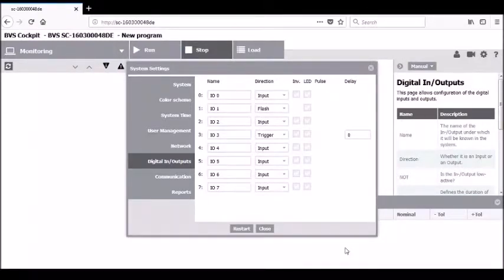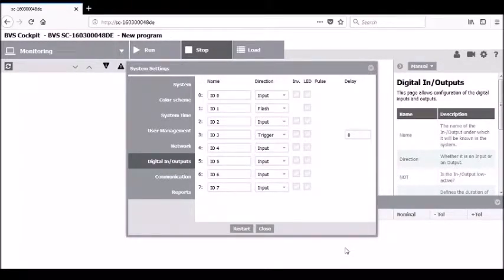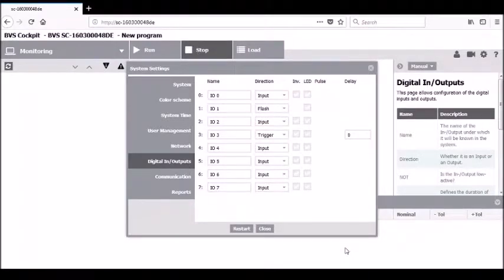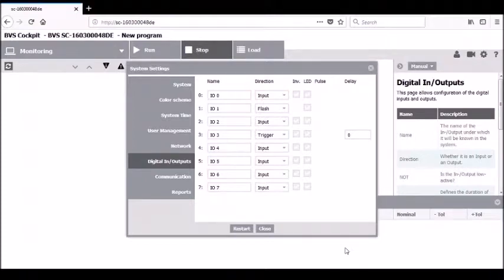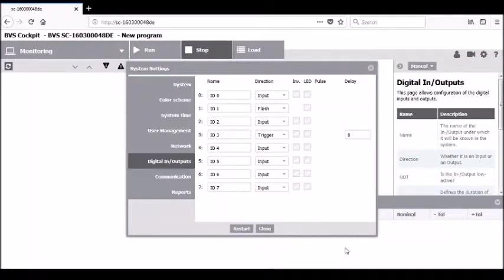In the case of an I/O field bus variant, only I/O 0 and I/O 1 go to a physical pin on the power connector through pin 2 and pin 4. Pin 6 and pin 7 are brought out through the I/O link port connector through pin 2 and pin 4.